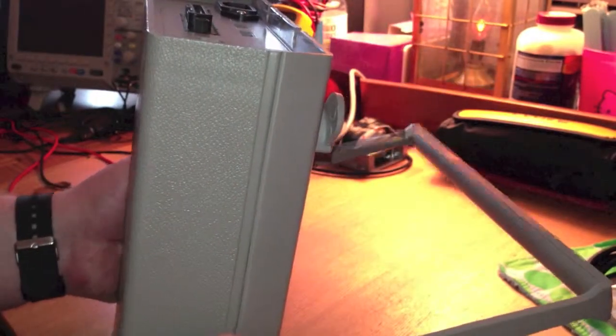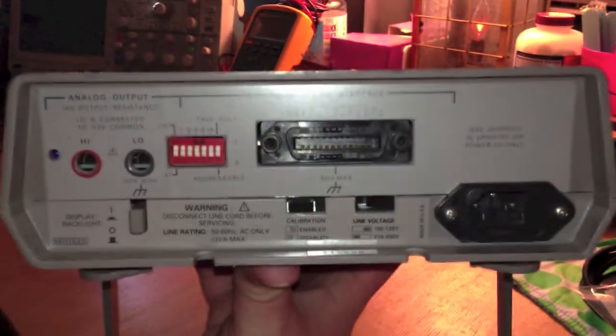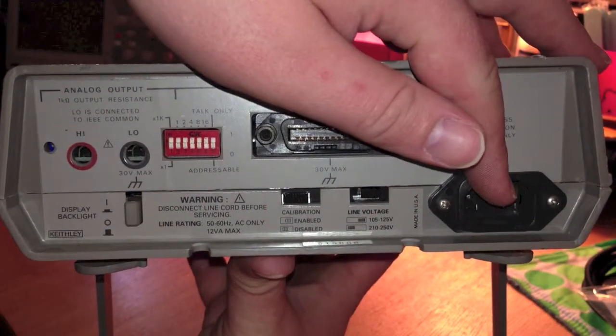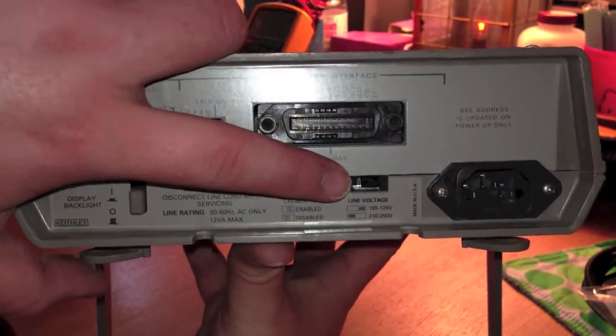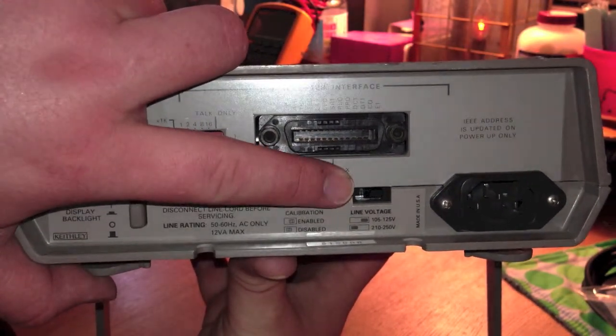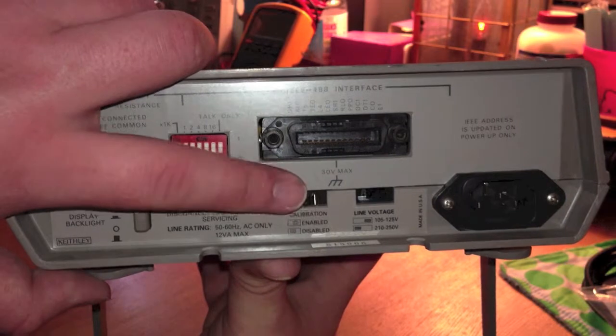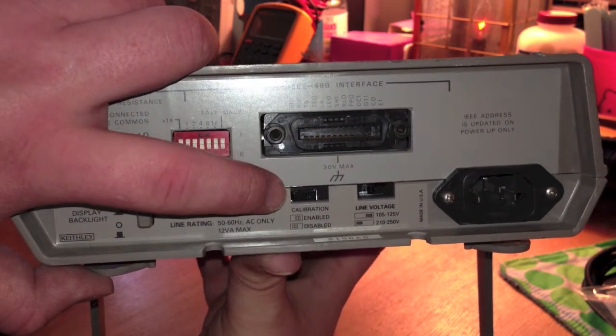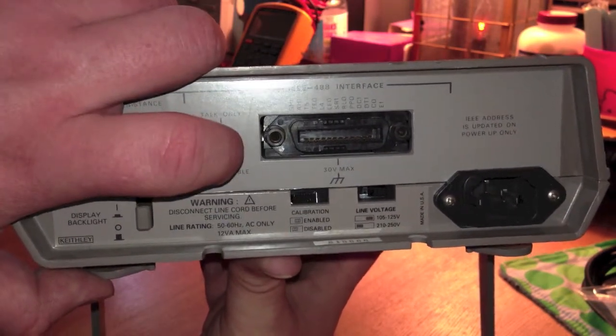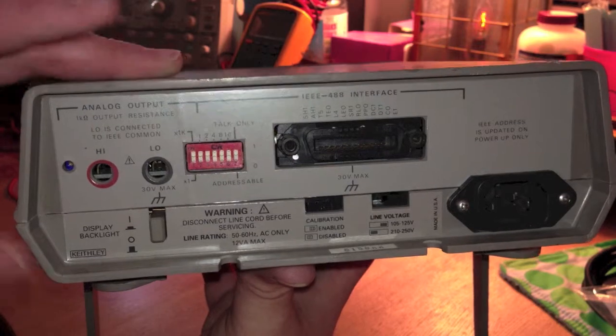And then we switch this around to the back. On the back here, we've got your normal IEC power connector. Over here, you can go between 210, 250, and 105, 125 with that switch. Now, this is interesting. This is your calibration switch. It should normally be in the disabled position over to where my finger is. Flop it over the other way, and that enables calibration. This turns on and off the backlight.